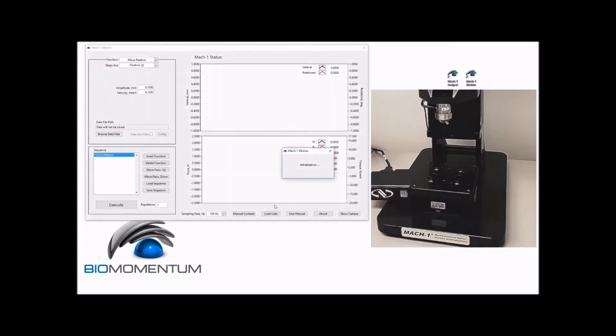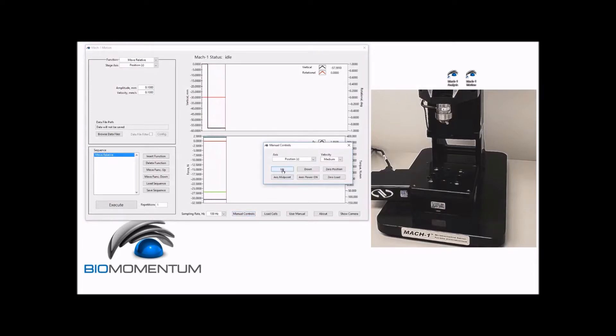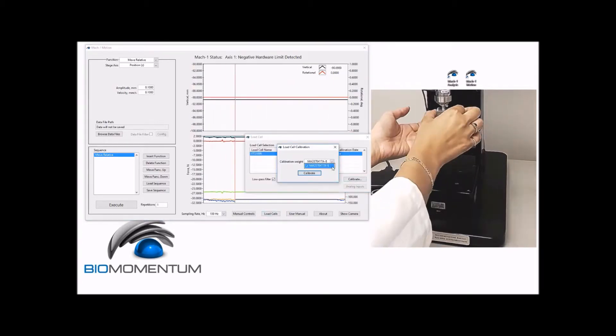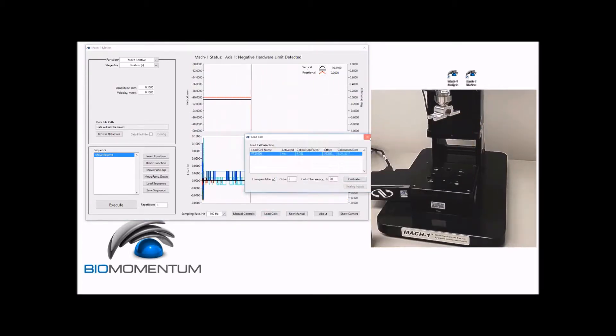Using the manual controls, raise the vertical stage to its maximum height using medium speed. Then verify load cell calibration as per the Mach-1 user manual.